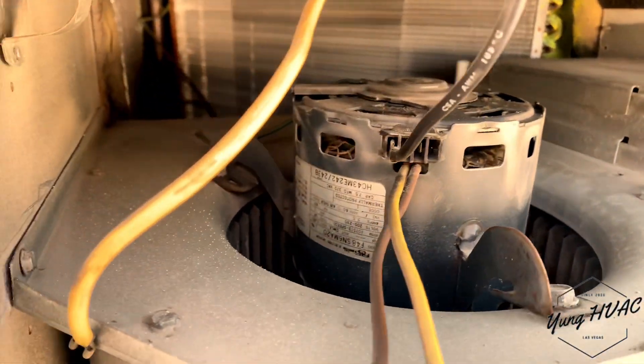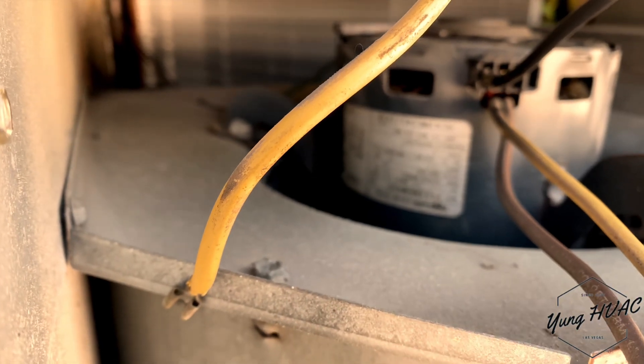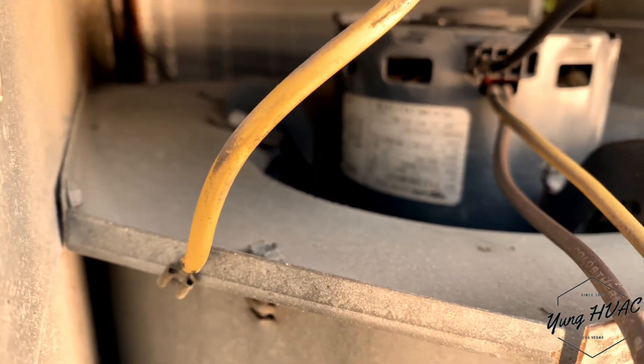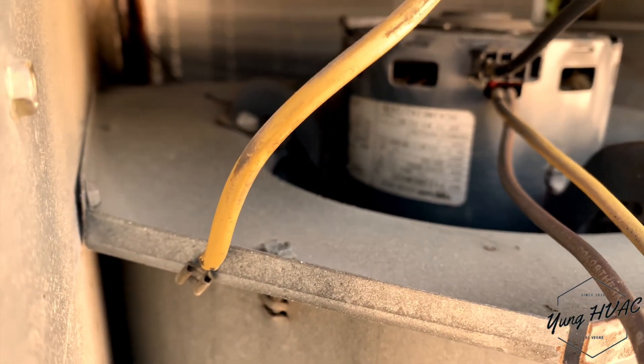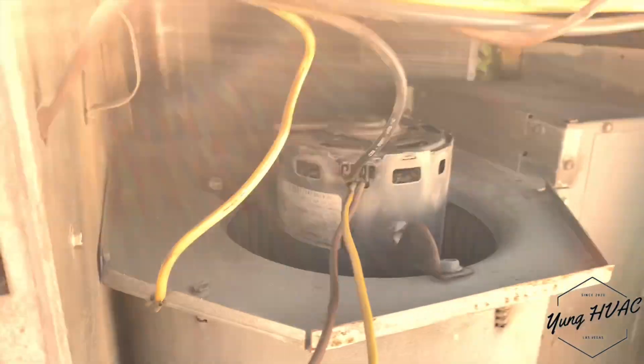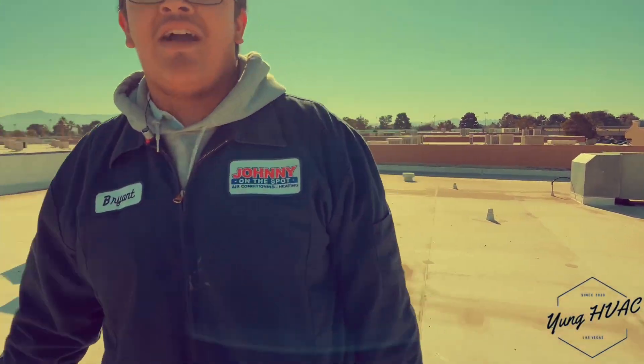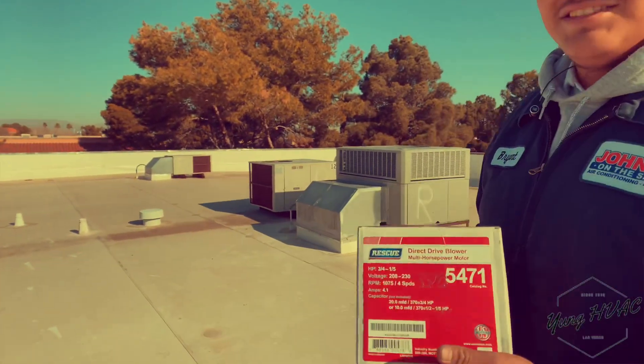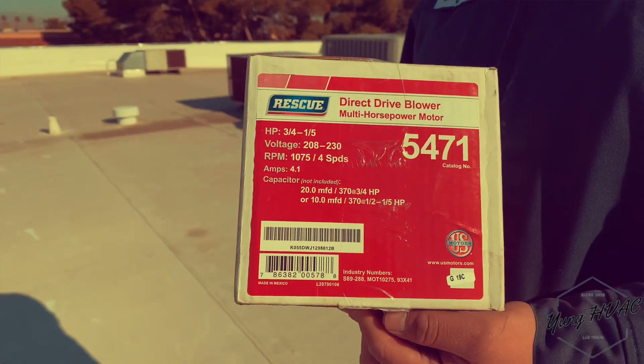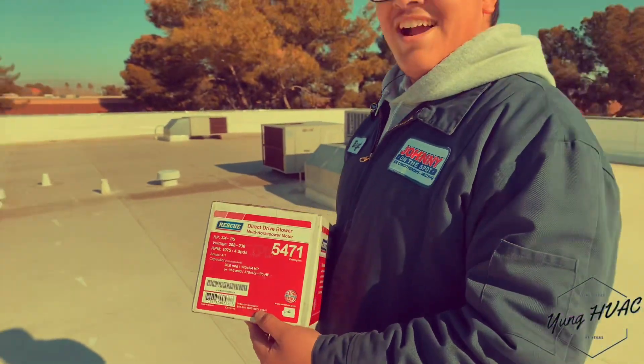Check that data tag — we got 208 to 230 volt, 1075 RPM, and 3/4 horsepower. Brian, what you got for us? We got a blower motor — this is just what we needed. Let's go ahead and do an unboxing video.